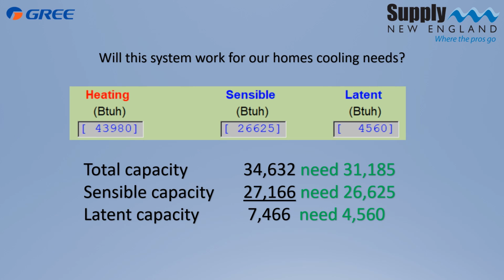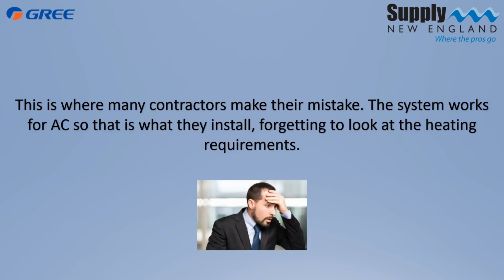The total capacity of the system is 34,632. We only need 31,185. We're covered. Sensible capacity, 27,166. We only need 26,625. Latent capacity of the system is 7,466. We only need 4,560. So does this system work for the cooling side of our home? Yeah, it works. This is where some people make their mistake. Oh, it works, this is what I'm going to install.